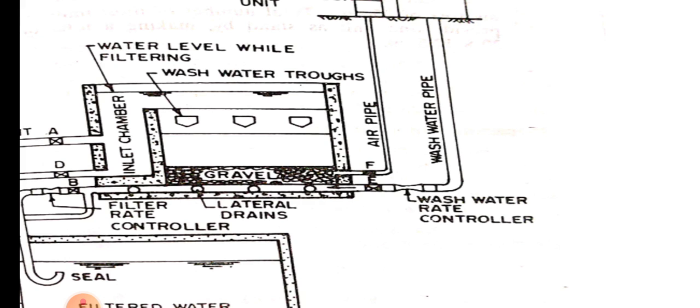This process of washing is continued until the wash water appears clear. As water and air enter the filter media and flow upwards, all the clogged particles and other dirt will mix along with the water, and this waste water will be carried away through the valve D. So this process of washing will continue until the water appears clear.